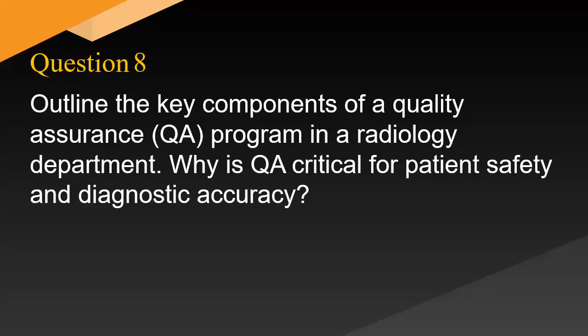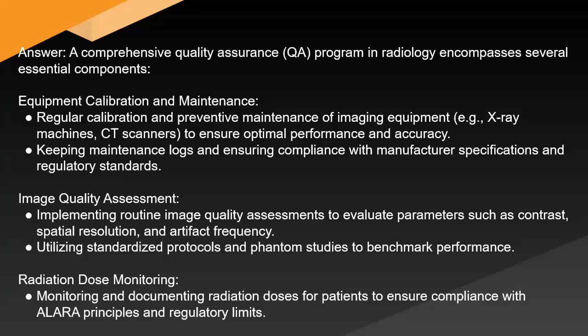Answer: a comprehensive quality assurance program in radiology encompasses several essential components: equipment calibration and maintenance, regular calibration and preventive maintenance of imaging equipment, e.g., X-ray machines, CT scanners, to ensure optimal performance and accuracy, keeping maintenance logs and ensuring compliance with manufacturer specifications and regulatory standards. Image quality assessment: implementing routine image quality assessments to evaluate parameters such as contrast, spatial resolution, and artifact frequency, utilizing standardized protocols and phantom studies to benchmark performance. Radiation dose monitoring: monitoring and documenting radiation doses for patients to ensure compliance with ALARA principles and regulatory limits, utilizing dose tracking software to identify trends and optimize protocols.